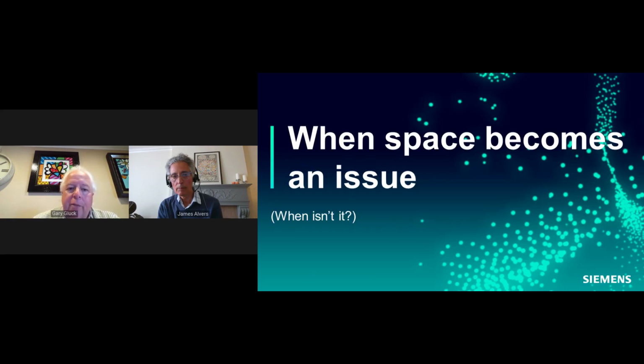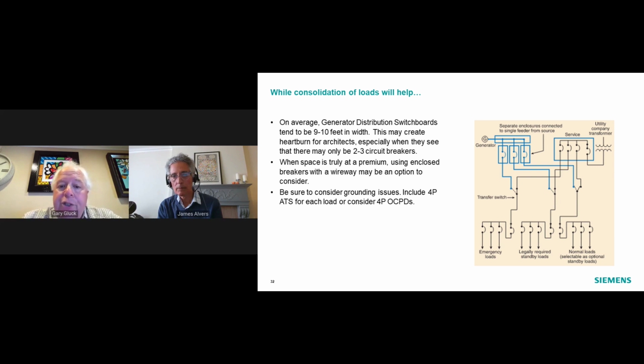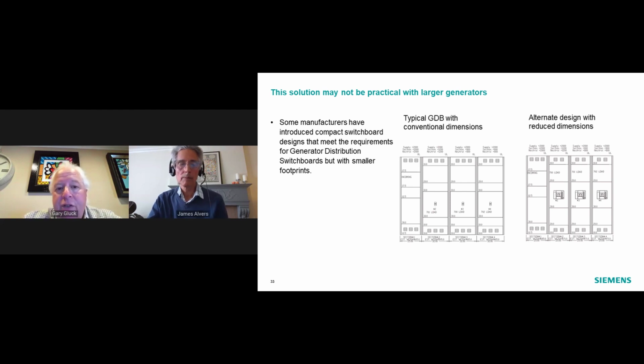Okay, so the final topic is when space becomes an issue, and frankly, when isn't it? On average, as I mentioned at the beginning of the presentation, switchboards can be anywhere from 10 to 20 feet. If space is truly at a premium and the system is not that large, you can use wireway and enclosed breakers in order to achieve a specific size. And that's going to be a fairly narrow solution. But in most cases, with most of the projects that we see, we're going to exceed that, and we're going to need to use switchboard construction. And this picture illustrates what we could typically see.